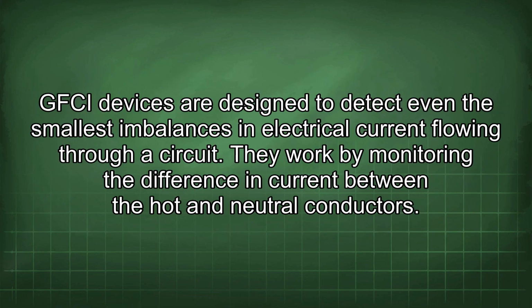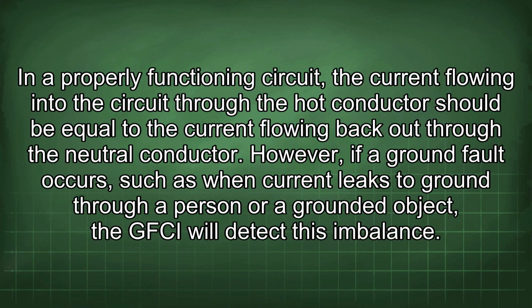GFCI devices are designed to detect even the smallest imbalances in electrical current flowing through a circuit. They work by monitoring the difference in current between the hot and neutral conductors. In a properly functioning circuit, the current flowing into the circuit through the hot conductor should be equal to the current flowing back out through the neutral conductor. However, if a ground fault occurs, such as when current leaks to ground through a person or a grounded object, the GFCI will detect this imbalance.